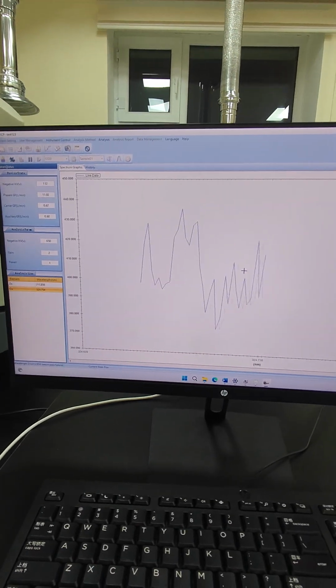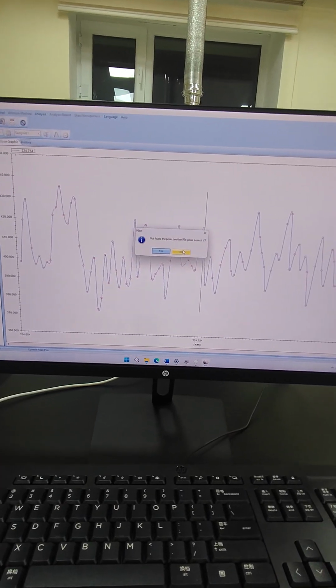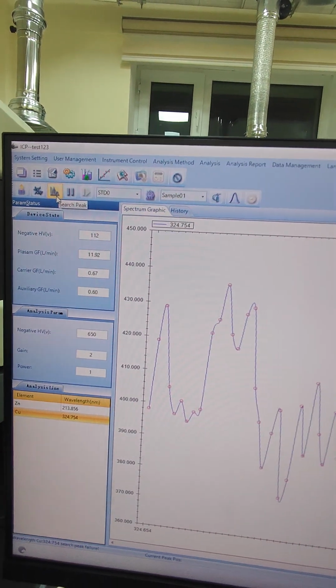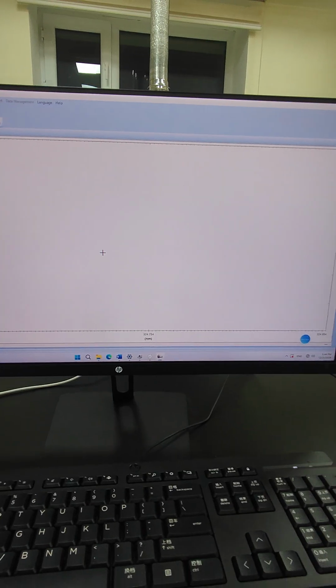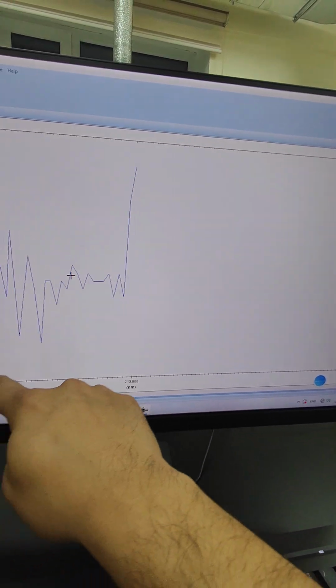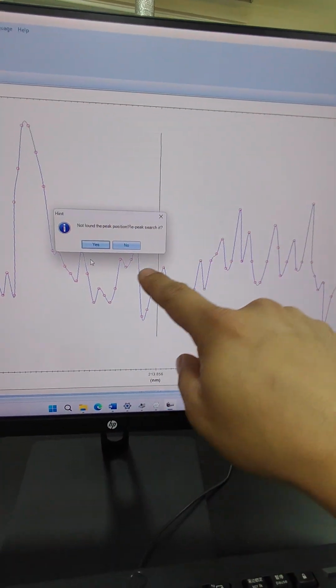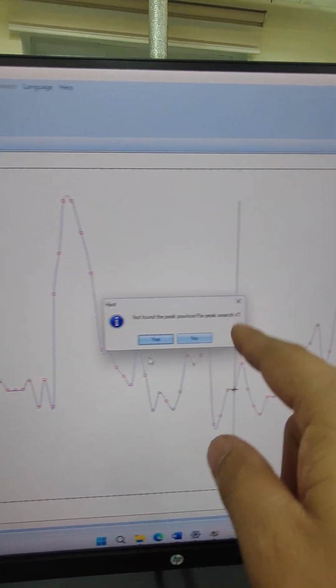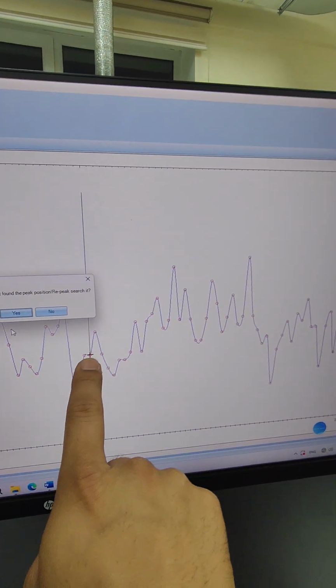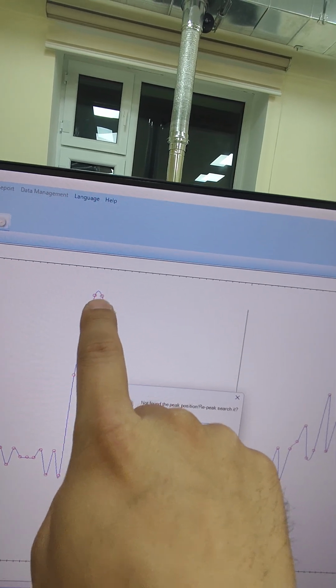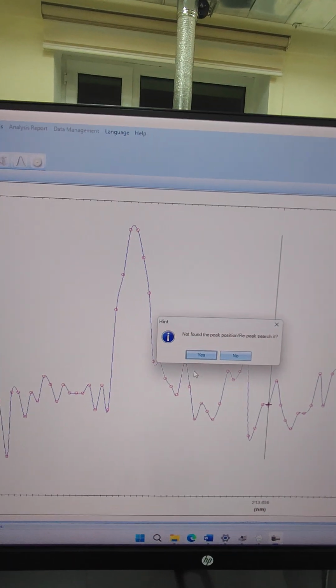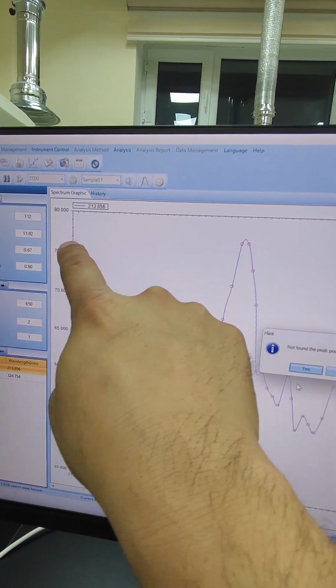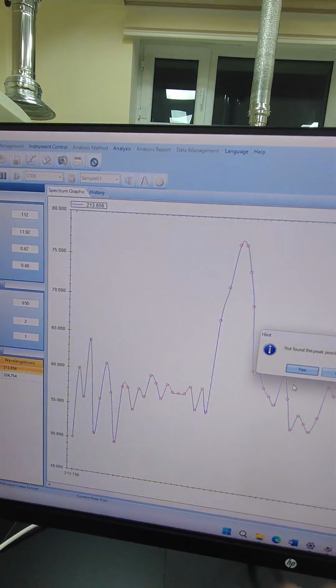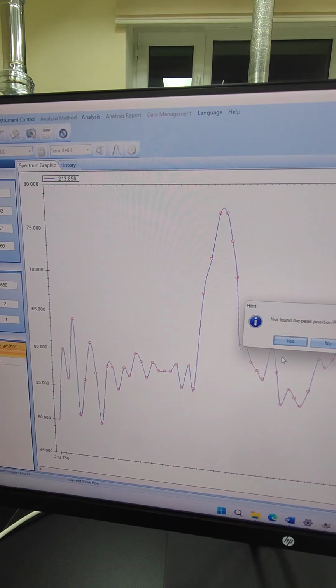And now here we press no. Every time before we do that, we need to proceed the search peak 3 times. The main target is that when it's going to find the peak, for example, this peak, there is a vertical line. The vertical line position should be at the middle of the peak. And you also need to notice the height position. For example, here is 2,000, 3,000, or 4,000. Now for example it's 4,000.